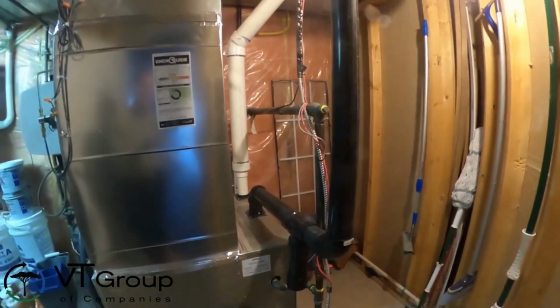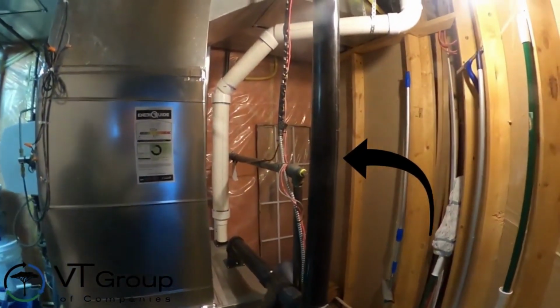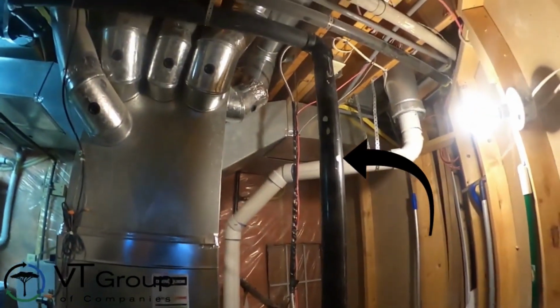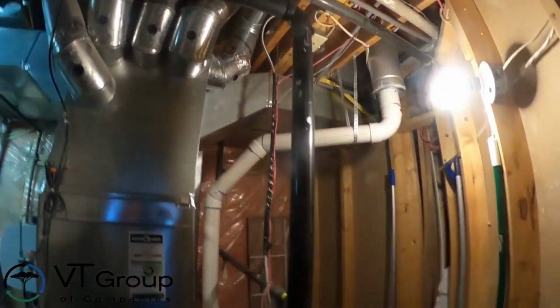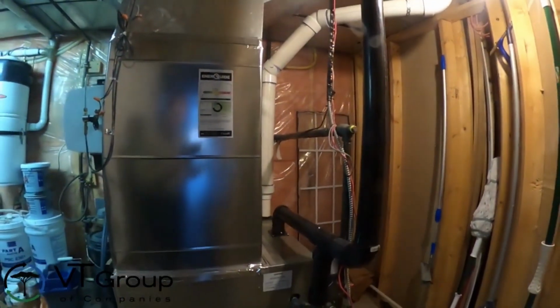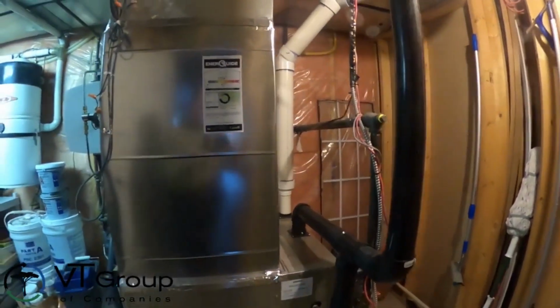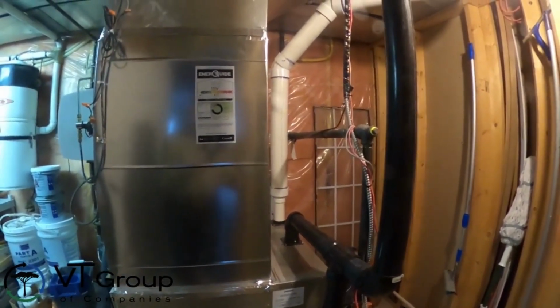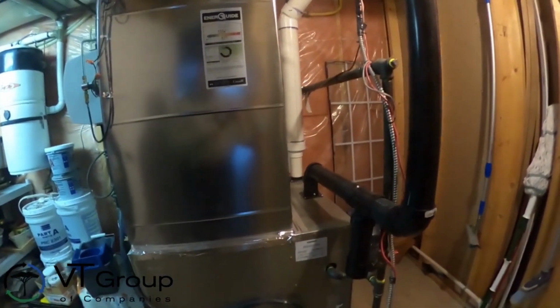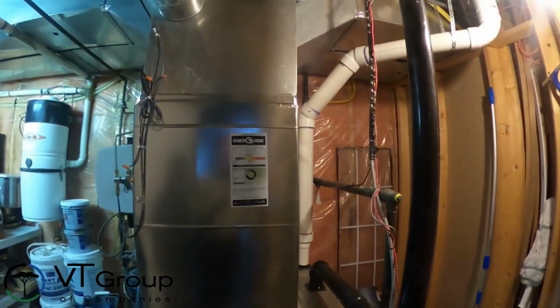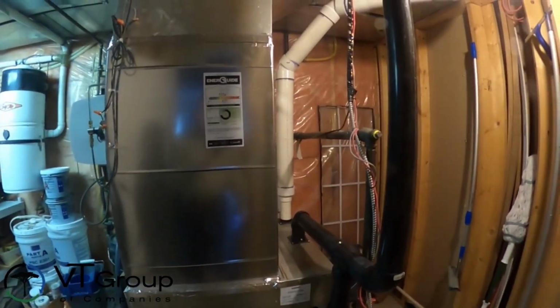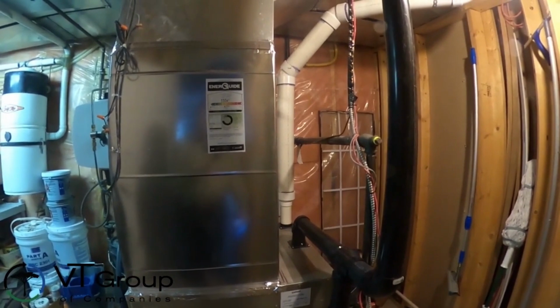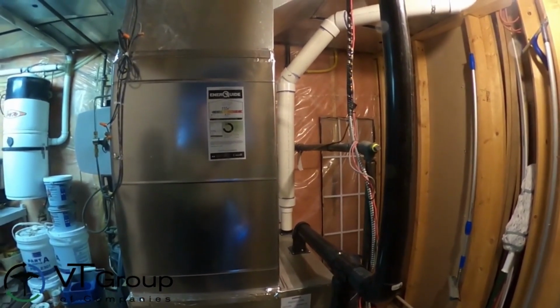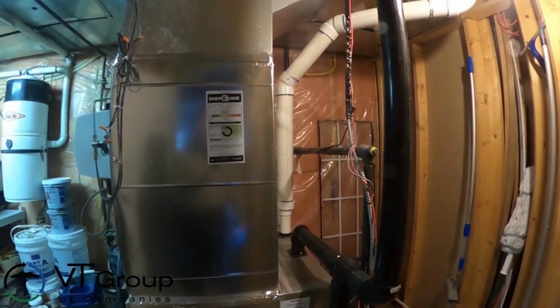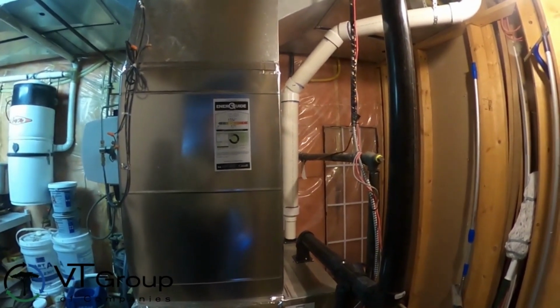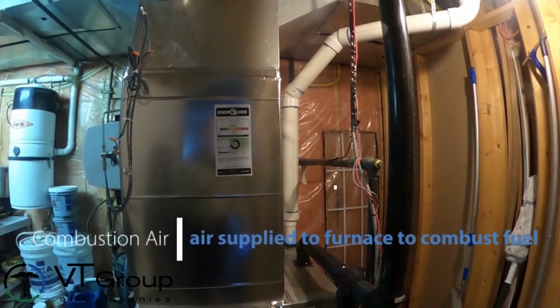This is what we saw in one of the other videos. This is the fresh air intake, air coming in from outside. So air goes in, and you can actually hear the furnace firing up there. In this case, we've got fresh air coming in, it gets burned in the combustion chamber and goes to the outside. So we can't even get combustion spillage on this, on the basis that it's a fully closed combustion chamber. I strongly recommend anybody installing a high efficiency furnace ask your contractor to do a 2-pipe system and not draw combustion air from the space.